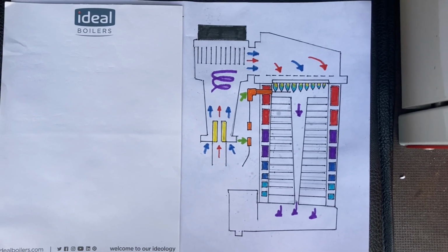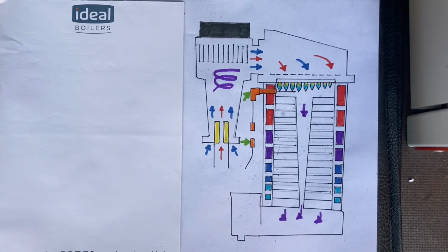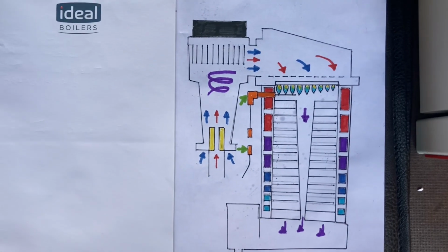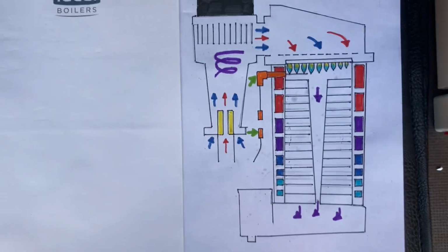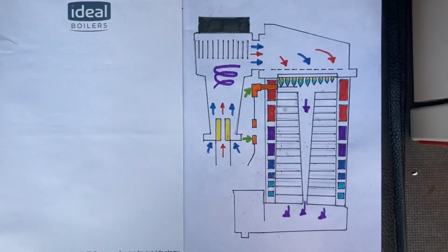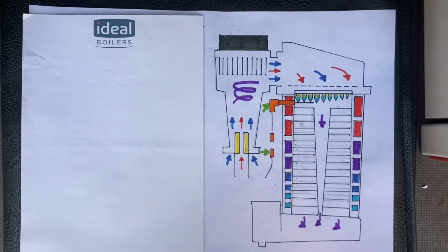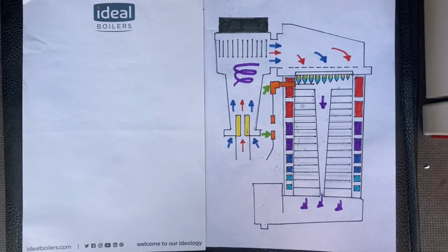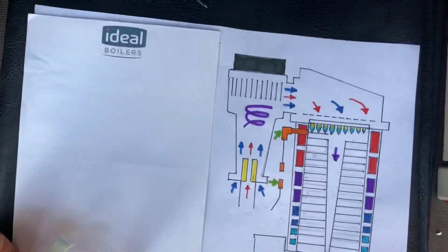But then it dawned on me that I've done so many of these ionization probes before. I know the readings: on a boiler at minimum fire, I should be getting through ionization 3 microamps on an Ideal Logic, and depending on the Logic, whether it's 24, 30 or 35, I know the maximum reading. So I've written it down here.